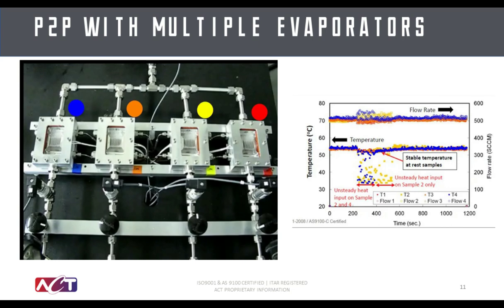As you watch the video, you'll see dots turning on and off, which is indicating the power being turned on and off to that particular evaporator. You'll watch the bubbles disappear in the evaporator as the power goes away. What you can see is that flow is not disrupted to the other components that still have their power. This is a big benefit of pumped two-phase cooling if designed properly. Let's watch the video.